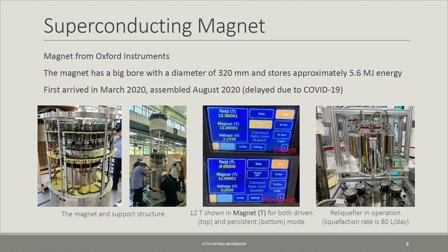The superconducting magnet from Oxford Instruments has a large bore of 320 mm. Although slightly delayed due to COVID, it was installed in 2020 and can reach 12 tesla in both driven and persistent modes. For the first results, data was taken starting in driven mode before switching to persistent mode. We also have a helium reliquefier in operation to conserve liquid helium, since the dilution fridge is a wet type.